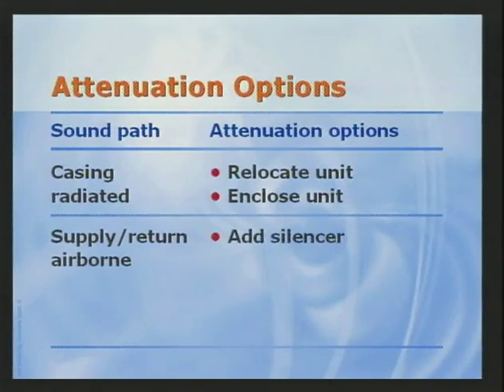Supply and return paths are best attenuated by modifying the ductwork. Adding a silencer is an option, but remember that the silencer adds static pressure. Be sure to properly select the fan to handle the added pressure drop, and remember that when a fan works harder, it makes more noise. Duct lining is essentially a zero pressure drop silencer that effectively attenuates duct-borne sound. Adding duct lining can be controversial because of IAQ concerns, but my advice is to find a way to keep the duct lining. Duct manufacturers are starting to make cleanable lined duct.